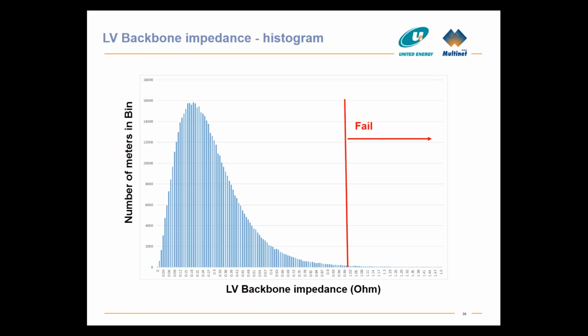We've used that same principle with our analytics, basically saying we can accurately measure the impedance. This is a histogram of all our impedances, typically about 0.2 to 0.25 ohms. Every one over 1 is a fail, and we started to dispatch that to the fault trucks.